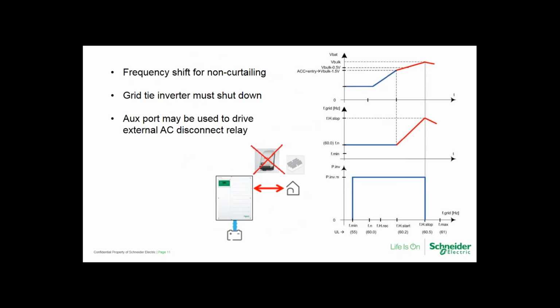So again, we're talking about the frequency shift algorithm. Here we see an XY chart for the function of frequency shift when using a grid interactive inverter without curtailment capability. We see that the inverter is at full power according to real-time solar production, while the frequency is within the UL parameters. When the battery voltage reaches bulk, the XW plus output AC frequency starts to increase. So if you're talking about a UL 1741 grid tie inverter at 60.2, I believe, it will shut down and it'll go into a countdown and it'll restart. So virtually any UL 1741 inverter will behave in that manner when the frequency shifts up.